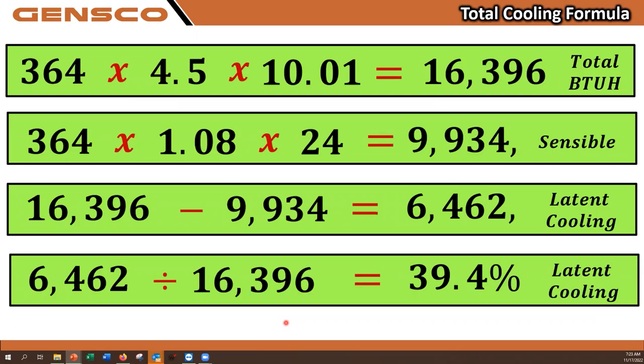What is my percentage of actual latent cooling? The amount of air conditioning that's being utilized to dehumidify the air. If I take this formula we just calculated for total cooling, and I use the same numbers we measured on the dry bulb side, 75 degree return air, 51 degree supply air, which had a 24 degree delta T, and I put that in the sensible formula, 364 times the constant of 1.08 times the delta T of 24, I get 9,934 BTUs of sensible cooling.